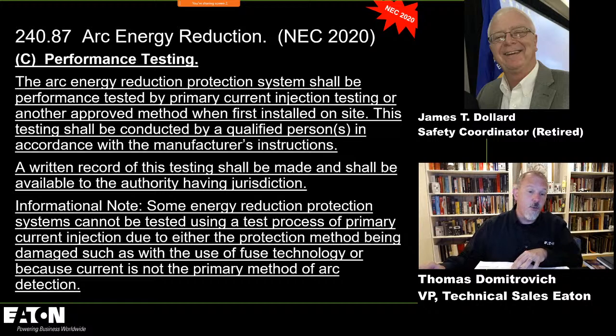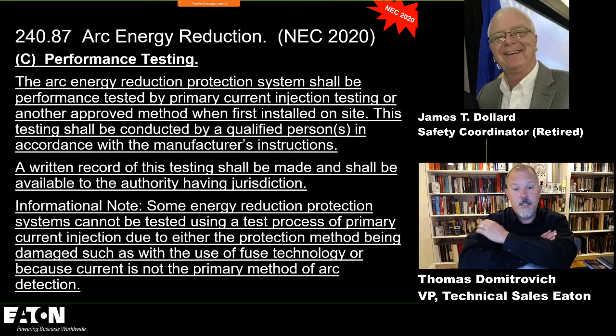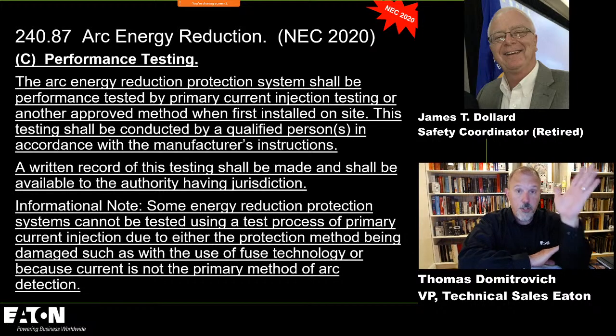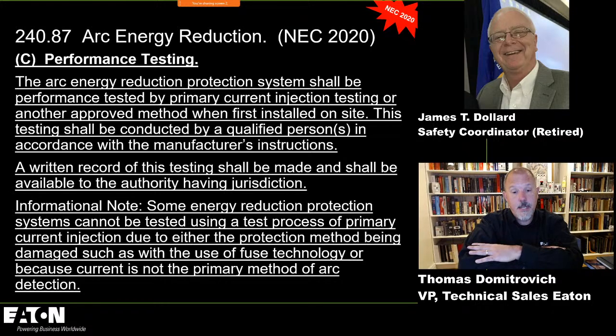But the other change that occurred was in 240.87, where that's near and dear to your heart. I know that. This was your brainchild back in the 11 cycle, I think it was, or 14. That's when it started. Yep. So they added performance testing for this equipment. And this was a panel 10 thing, where panel 10 has primary current injection testing for ground fault protection of equipment, which a lot of people still don't do. They keep missing that fact and just pressing a button. But in any case, they said, hey, if we're doing that testing over there, 240.87 is all about the electrical worker. We should be requiring some performance testing on first installation at least. And then there's obviously 70B, which takes over from a maintenance perspective. But I think this change will go a long way to making sure that a lot of these technologies will actually do what they're designed and supposed to do after the first installation at least.